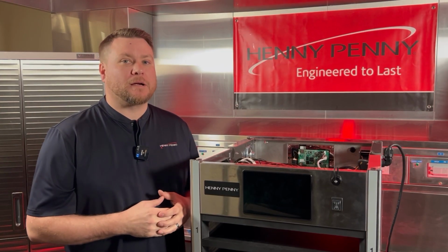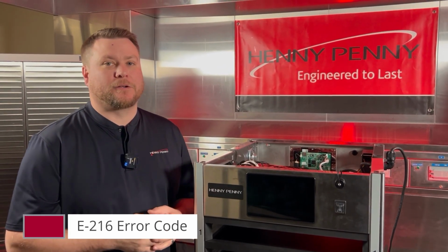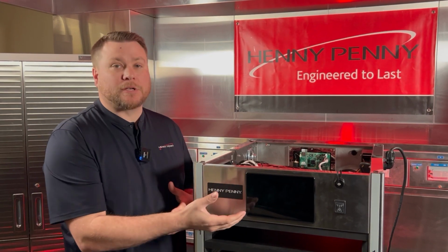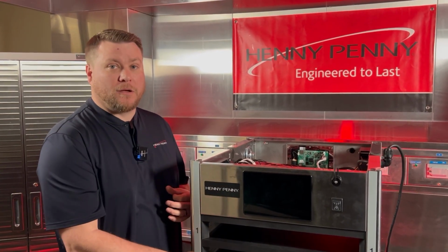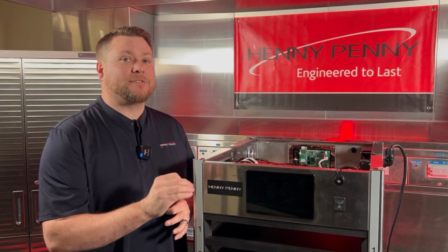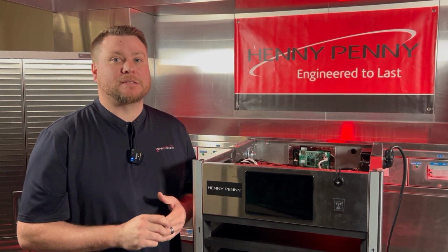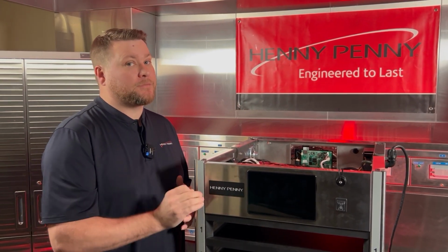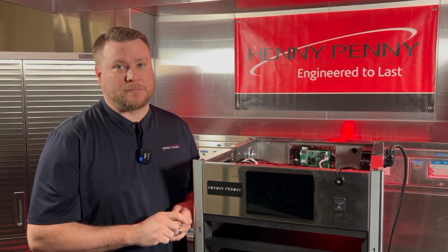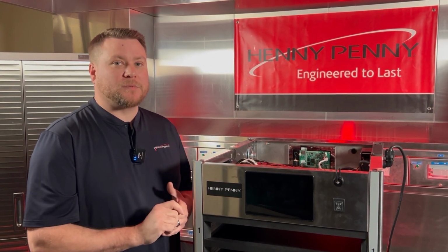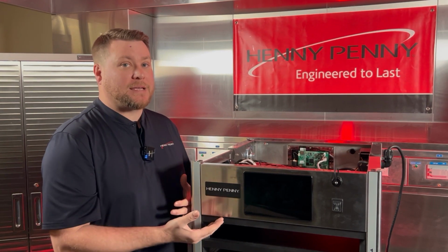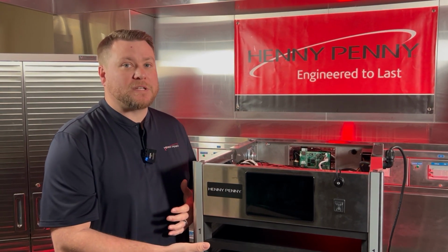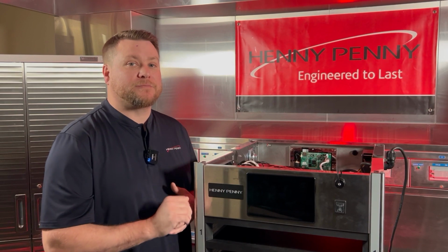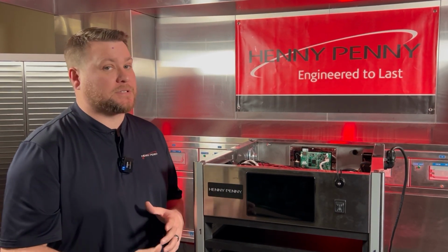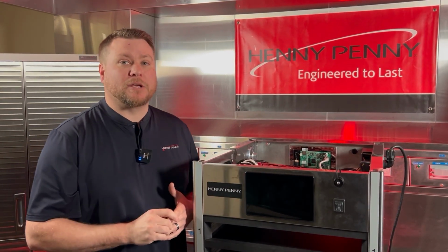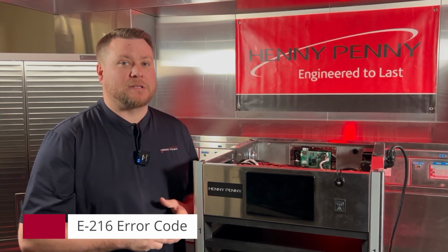In this video, we're going to talk about the E-216 error code. Basically, what that is, is when the control has seen one of our shelves drop more than 11 degrees Fahrenheit or 6 degrees Celsius below the set point temperature for longer than 15 minutes. So those few things have to be met. It has to be below that set point temperature for longer than 15 minutes by more than 11 degrees Fahrenheit or 6 degrees Celsius. If that happens, then it's going to generate the E-216 error code.